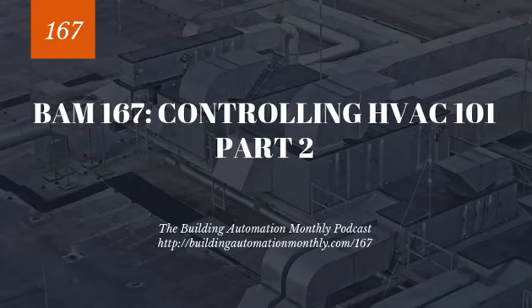So, as I mentioned, we also have mixed air units. Mixed air units exist to help us avoid conditioning unneeded outdoor air, and they also allow the reuse of preconditioned airflow. So if you're wondering why we use mixed air units, that's why. The main reason is the reuse of preconditioned airflow. If you have a tight envelope in your building and it's not really slipping out, and you're stopping infiltration and exfiltration, you've got a perfect balance of your building, then you want to reuse this preconditioned air that's already in there.